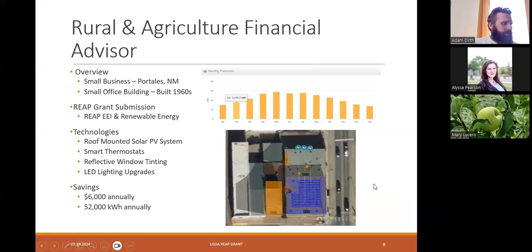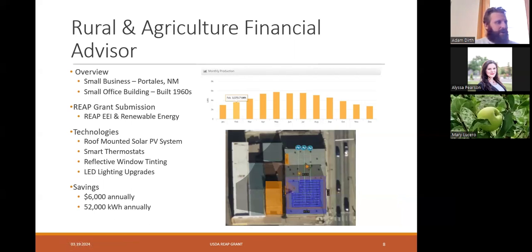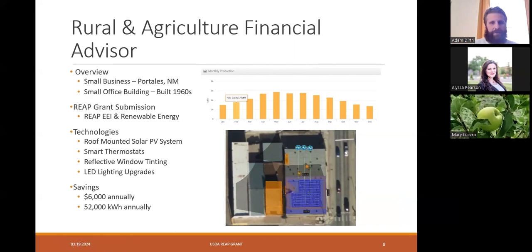Here is the solar system we designed and the monthly energy production from the system. They are going for both the energy efficiency and renewable energy grants, with technologies including solar PV, smart thermostats to bring the temperature down or up at night when the building is not occupied, reflective window tinting, and LED lighting upgrades. We're estimating they'll save $6,000 annually at this office and 52,000 kilowatt hours of consumption from the grid.